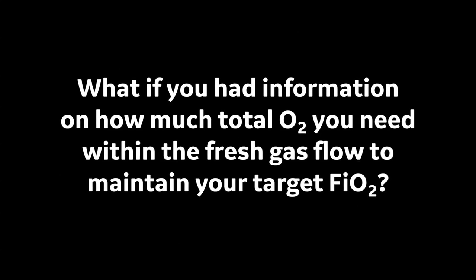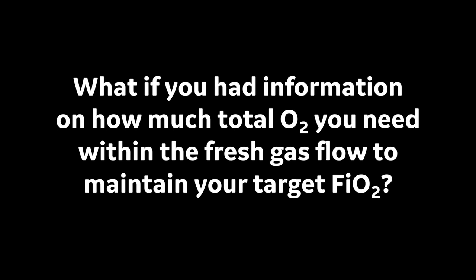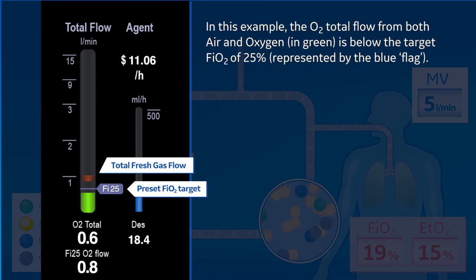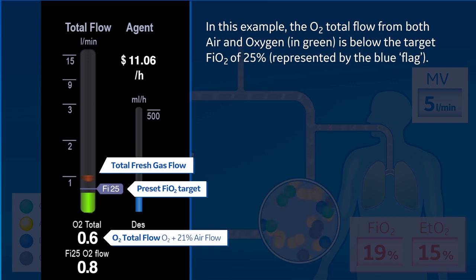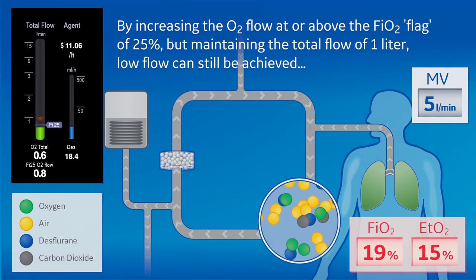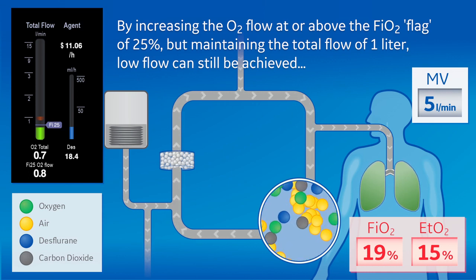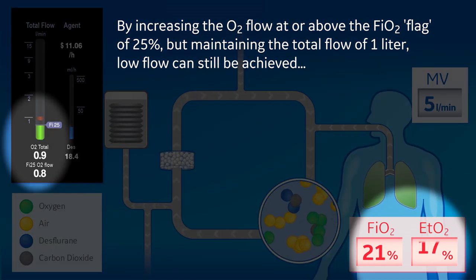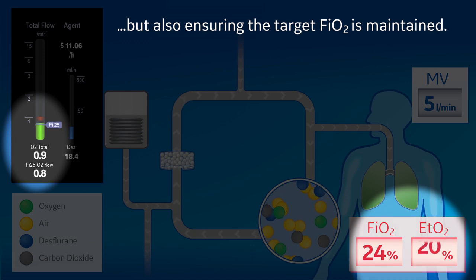But what if you had information on how much total oxygen you need within the fresh gas flow to maintain your target FiO2? EcoFlow provides data on the total oxygen required within the fresh gas flow to help ensure the minimum FiO2 target setting is achieved. In this example, the O2 total flow from both air and oxygen in green is below the target FiO2 of 25%, represented by the blue flag. By increasing the oxygen flow at or above the FiO2 flag of 25%, but maintaining the total flow of one liter, low flow can still be achieved while also ensuring the target FiO2 is maintained.